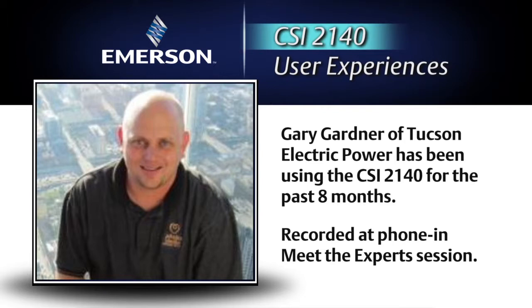For doing an ODS with the 2130, we've done quite a bit of ODSs here at our facility where we found equipment problems or different things and we want to see how it's moving. With the 2130, of course, we set our reference point and then we roamed — for one accelerometer we roamed with the other accelerometer. We had to put it in the horizontal direction, the vertical direction, and the axial direction for every single point we're going to plot out in our ODS. It's very time-consuming; you're actually taking three readings for every point, and you could have hundreds of points to collect — 300 to 400 data collection points takes quite a bit of time.